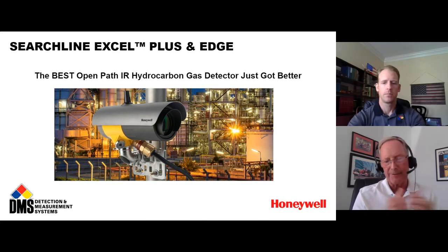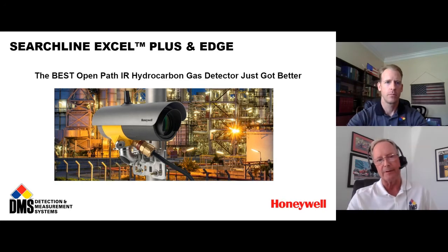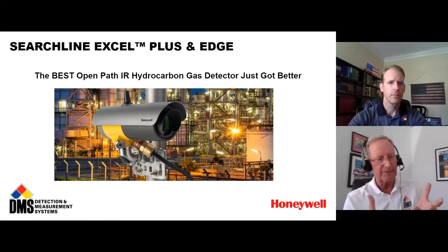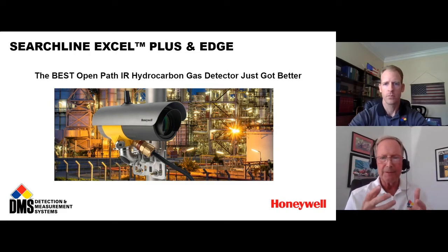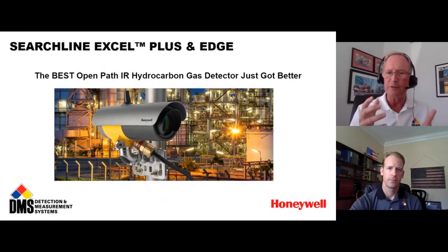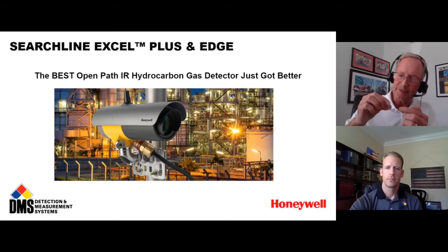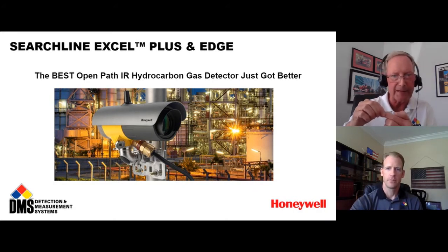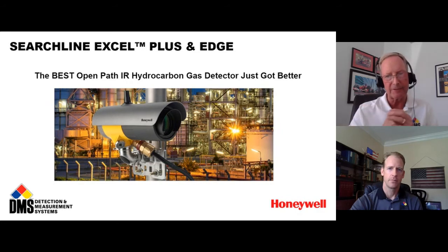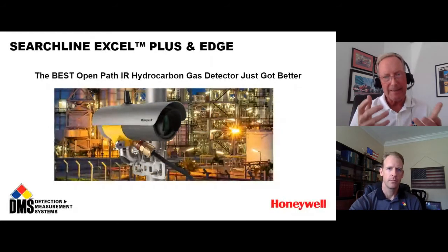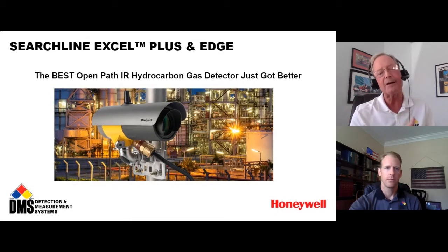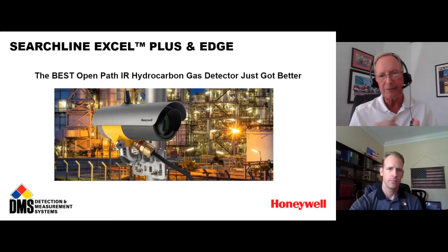And it's interesting. Throughout my career, I've had a number of occasions where I've had a customer looking at a detector, and he's going, "Wow, that's really a neat point gas detector, maybe a point hydrocarbon detector." And what's the area coverage of this detector? Is it 10 feet, 20 feet? What's the area coverage? And I explained to them, well, actually, the area coverage is the size of the hole that the gas goes in the gas detector to where it gets to the sensor where the sensor can respond. In other words, a point gas detector, whether it's a hydrocarbon detector or a toxic gas detector, has no area coverage. So where the gas detector is placed is critical.